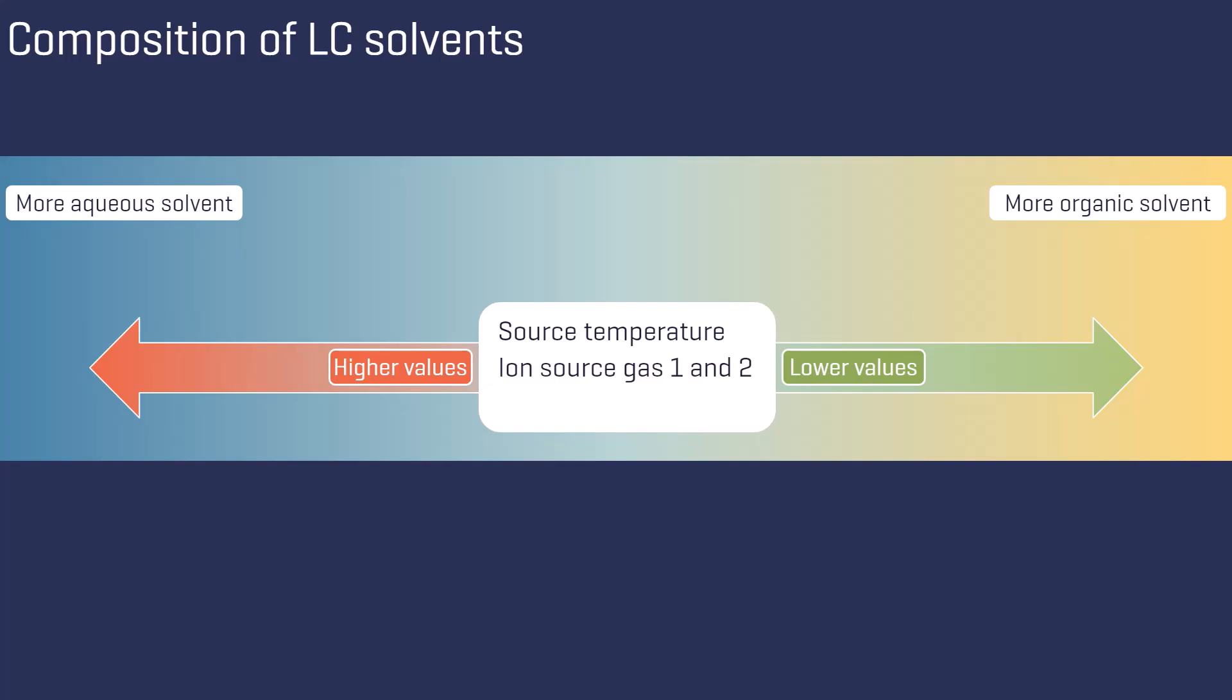This means that the source temperature and ion source gas 1 and 2 need to be lower the more organic solvent is entering the ion source. Additionally, less curtain gas is required since fewer larger droplets need to be prevented from entering the mass analyzer.